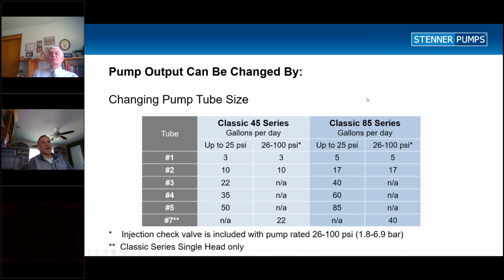Now, when we talk about sizing, this chart gives us a good breakdown as far as how to size the pump. So once again, in the water conditioning market, the tubes that we would use most frequently would be a number 1, 2, and 7 tube. Those are the only 3 tubes that you would need to worry about if we're operating in that 40 to 60, 40 to 70 PSI range.